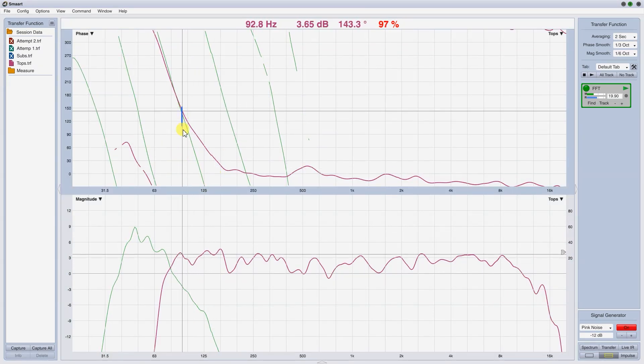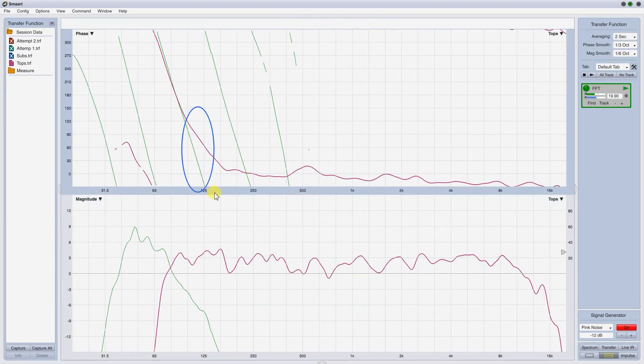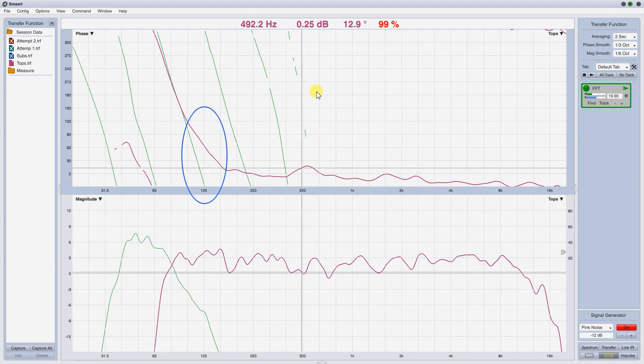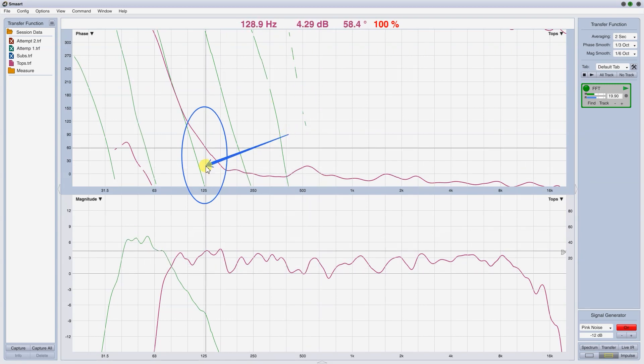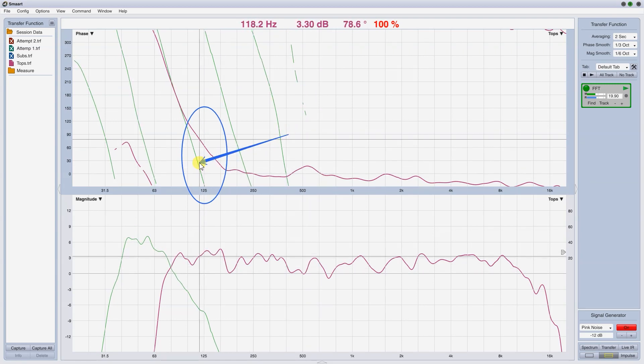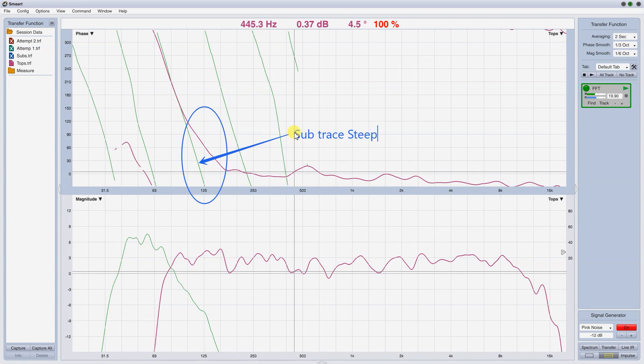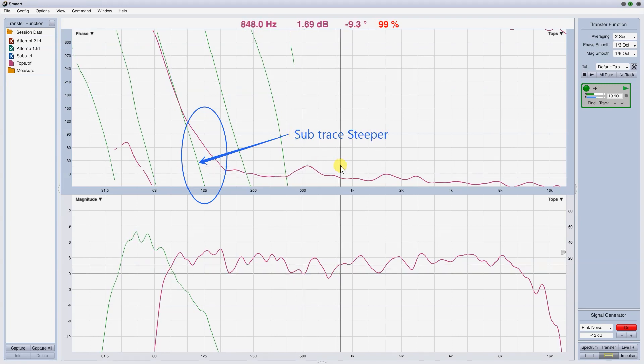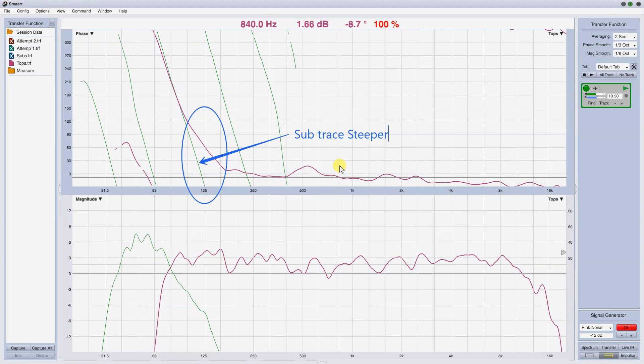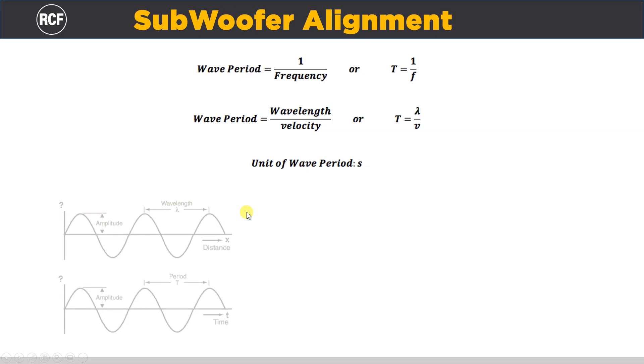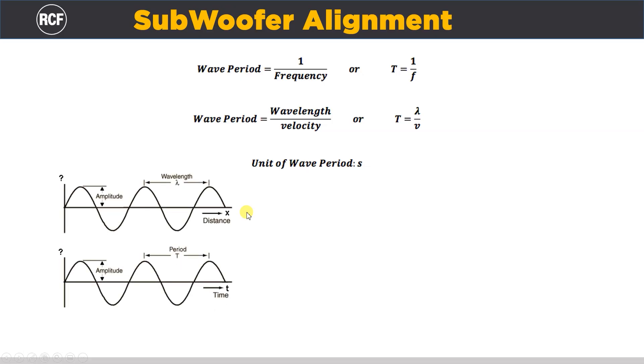Now, the sub-trace is steeper here, so we have to reduce the delay. But we remember that the first attempt with one less cycle was not good. So, let's try to reduce the delay by half cycle, which is 6.25 ms, and reverse the polarity.